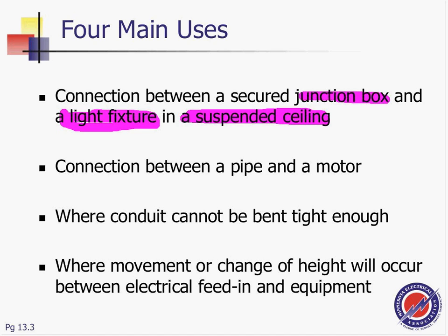Between a pipe and a motor. As I said, here's my disconnect coming over here. Here's my EMT conduit. Here's my air handling unit or chiller or whatever, or pump, and you flex it. You're here and you flex it all the way and tie it to the equipment. For what? For flexibility, number one. For vibration, number two. So, ease of movement if you need to move the machine to clear anything and so forth: ease of movement, flexibility, and absorbing the vibration.